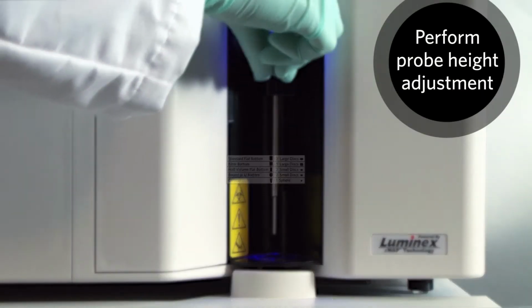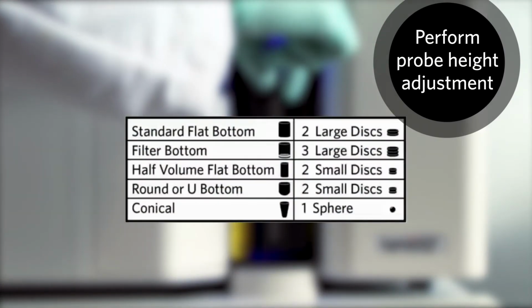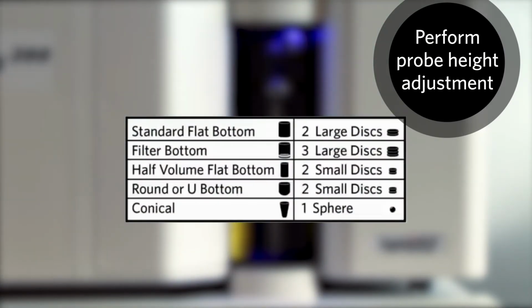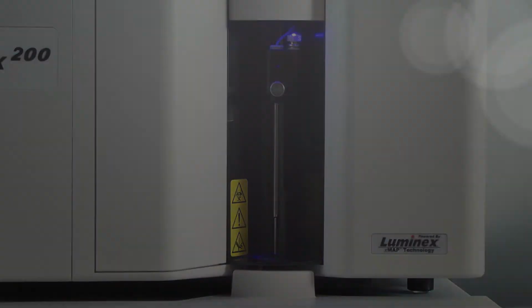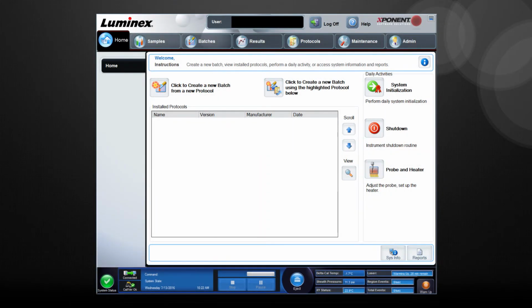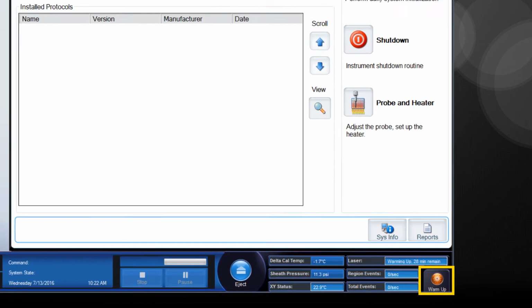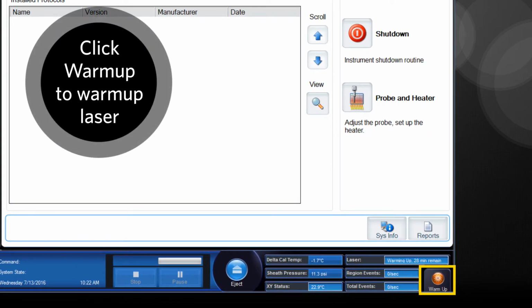Verify the sample probe height has been vertically aligned for the plate used by performing a probe height adjustment. Additionally, if the system is powered on but idle for more than 4 hours, click Warm Up. Wait 30 minutes for the Luminex 200 analyzer and optics systems to warm up.